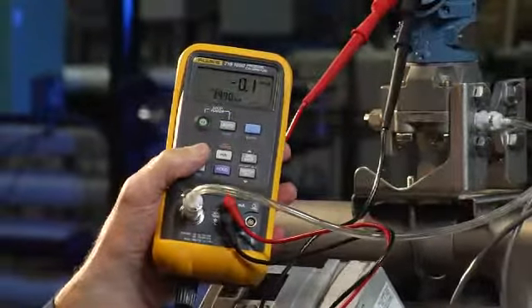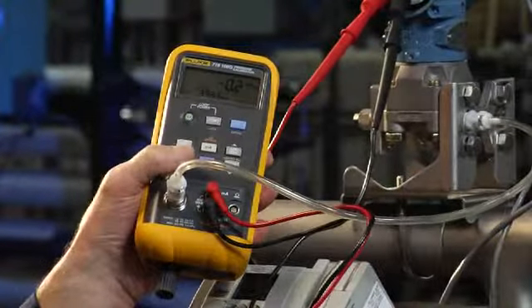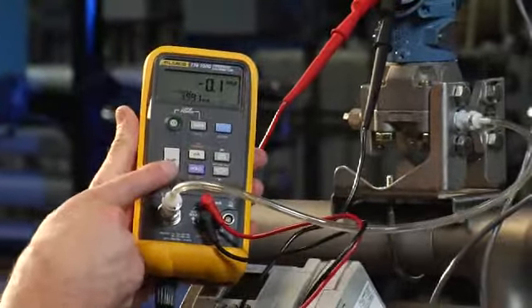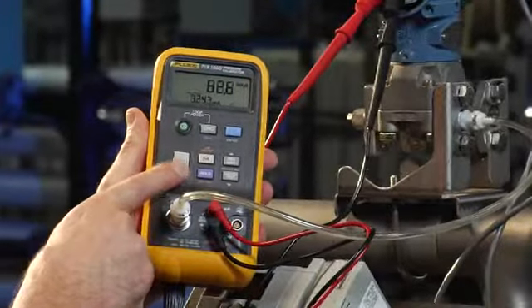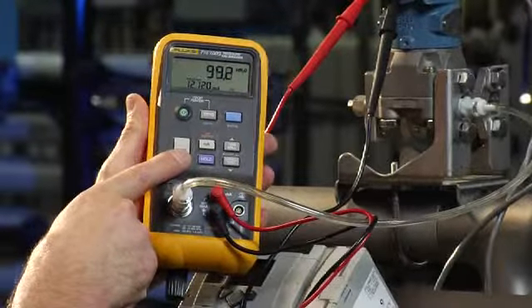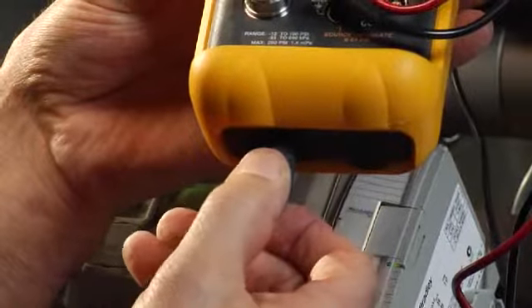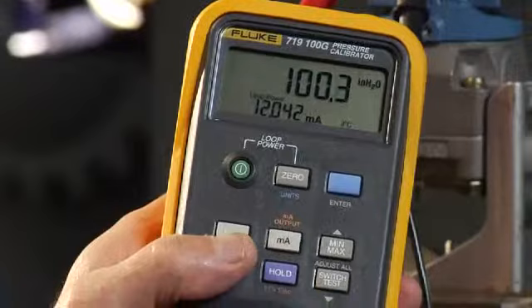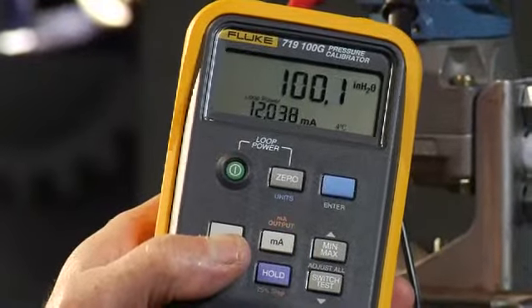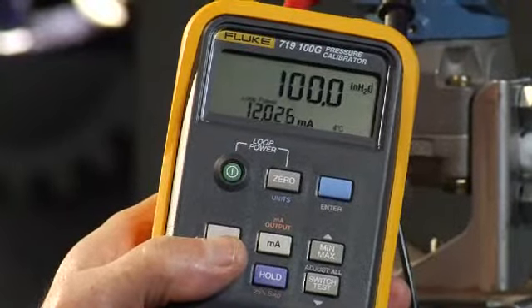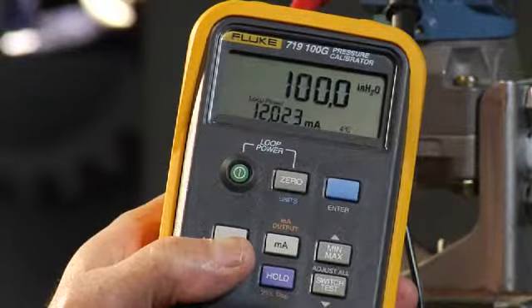The next test point, 50%, is 100 inches of water. We'll use the electric pump to generate 100 inches of pressure. Once the 719 gets close, you can use a vernier to adjust exactly 100 inches of water and verify for 12 milliamps. Any deviation from 12 milliamps being measured is calibration error in the transmitter.